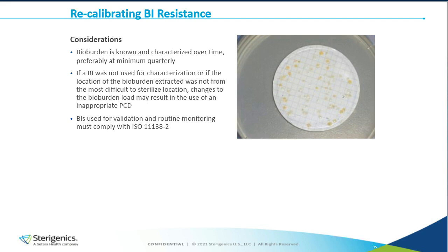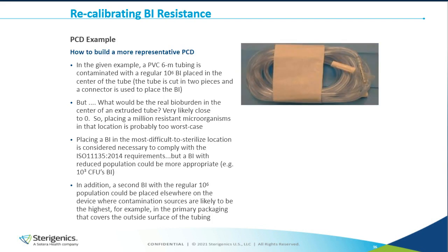And control of the bioburden is really key and essential, because I have heard several times that because we are using 10 to the 6 BIs, we can probably go away from bioburden testing, but that is not true at all, because even if we have a lower count of bioburden, we could still have resistant organisms in the bioburden. So it is still mandatory and a regulatory requirement to test the bioburden on a regular basis.